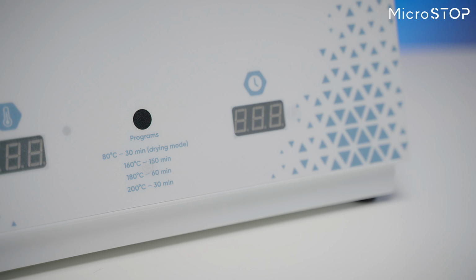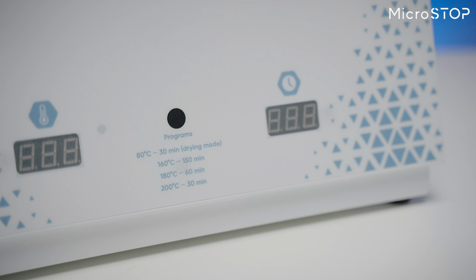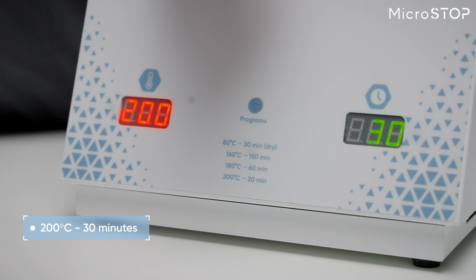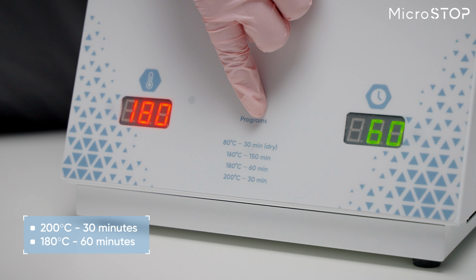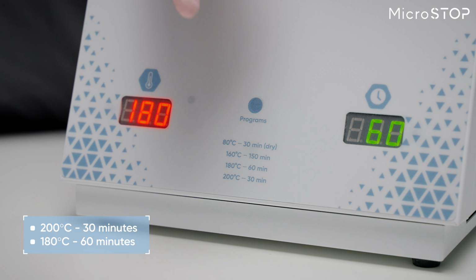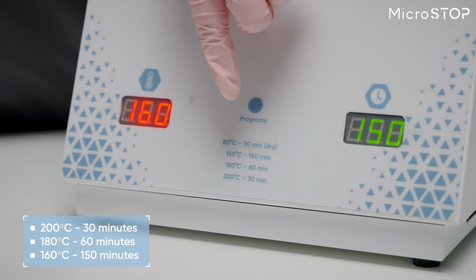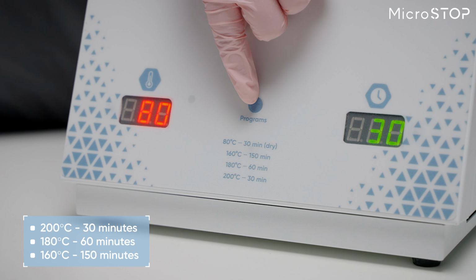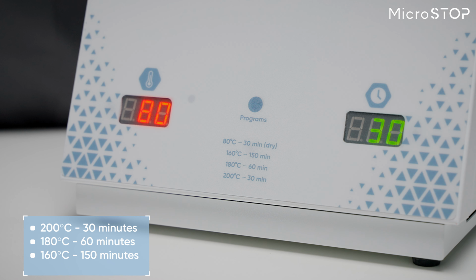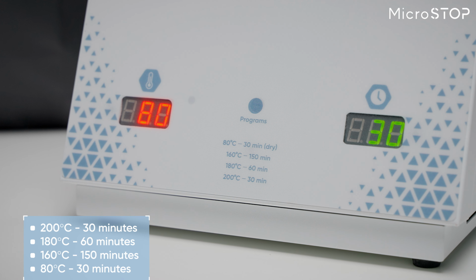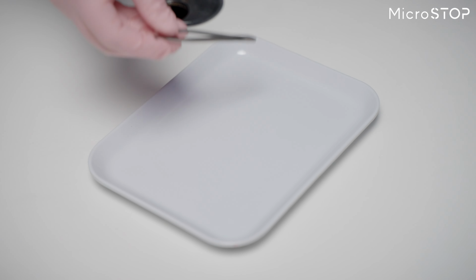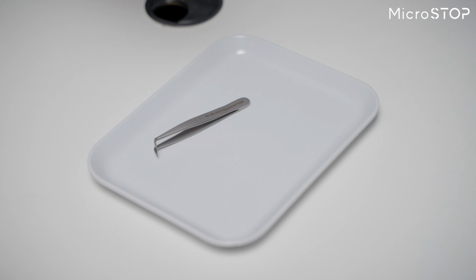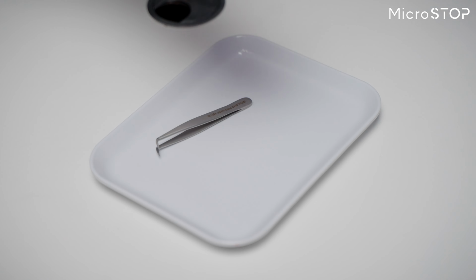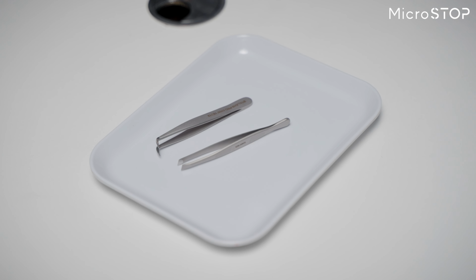All these models have 3 programmed sterilization temperature and time modes that meet European requirements: 200 degrees Celsius 30 minutes, 180 degrees Celsius 60 minutes, 160 degrees Celsius 150 minutes. Besides, Microstop sterilizers have an additional drying mode, 80 degrees 30 minutes. As before sterilization, the tools must not only be disinfected and clean, but also completely dry. The drying mode makes the daily work of the nail technicians easier and the process faster.